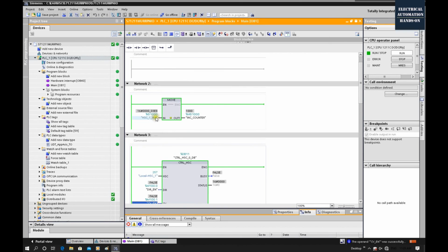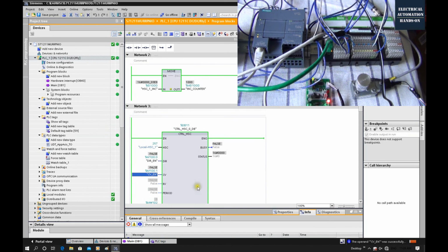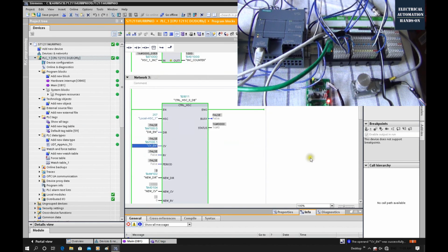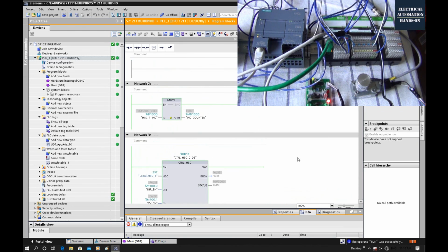And then this incremental encoder value channel can be loaded from that retained value. This is a very common way to use this CV to retain the incremental encoder value to this channel back. And now if I turn on the motor, and then go back here, we can see this counter is counting up.